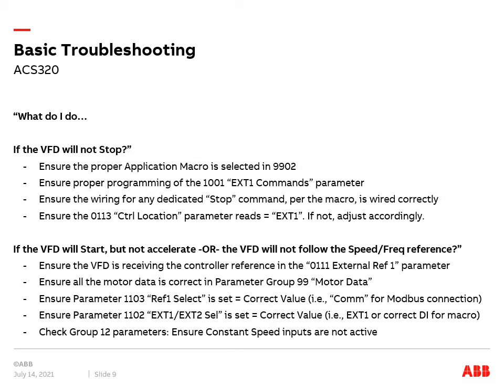What do I do if the VFD will not stop? Ensure the proper application macro is selected in parameter 9902. Ensure proper programming of the 1001 ext1 commands parameter. Ensure the wiring for any dedicated stop command per the macro is wired correctly. And lastly, ensure that the 0113 control location parameter reads equal to ext1.